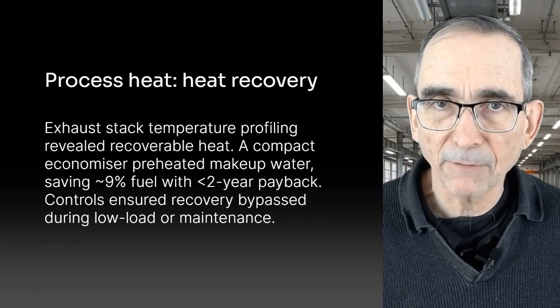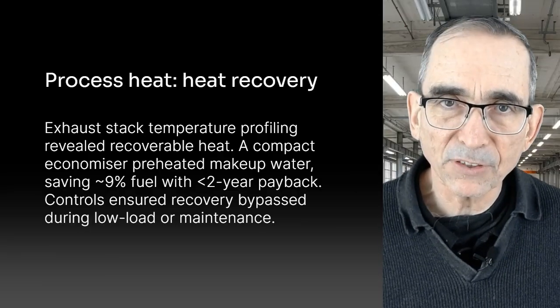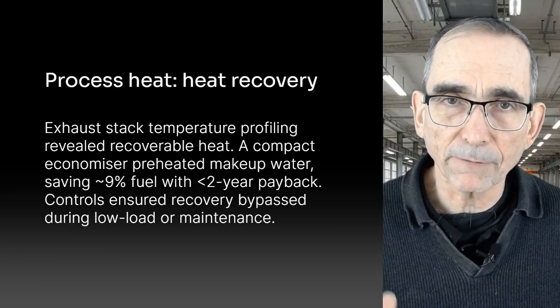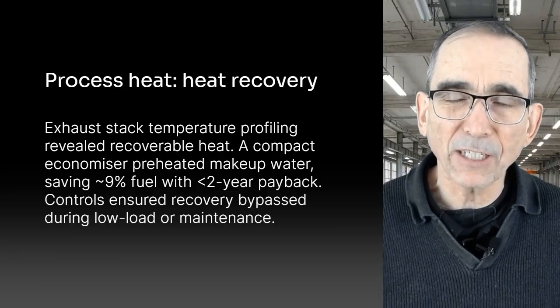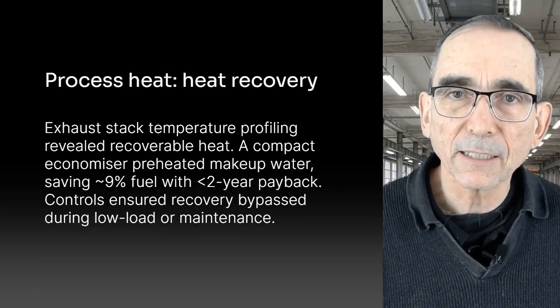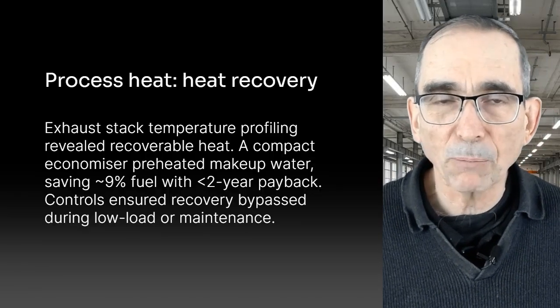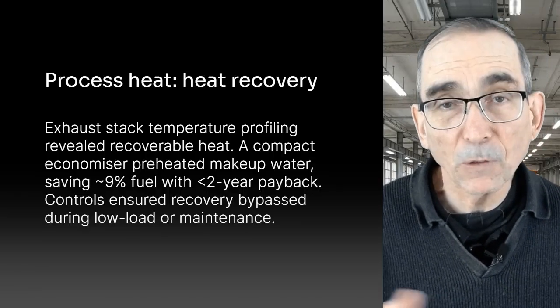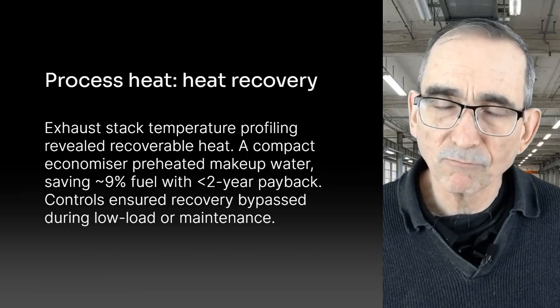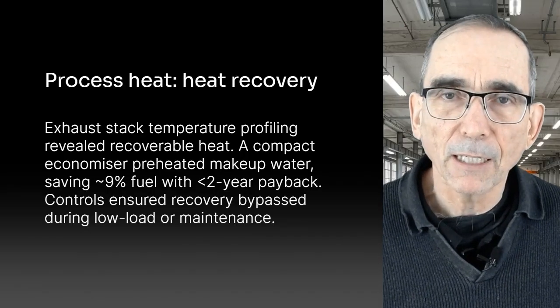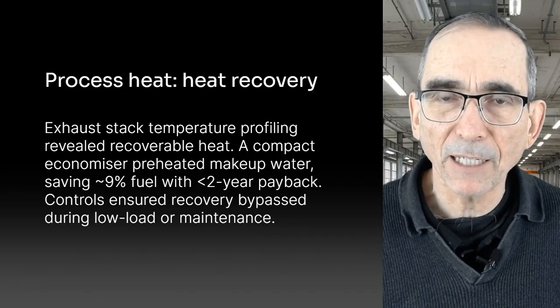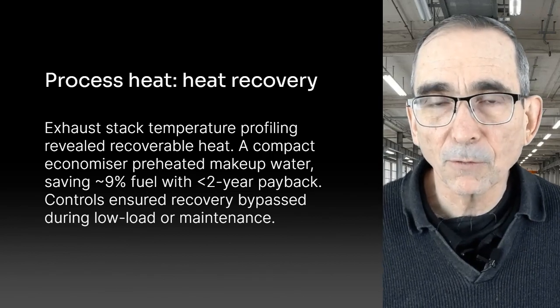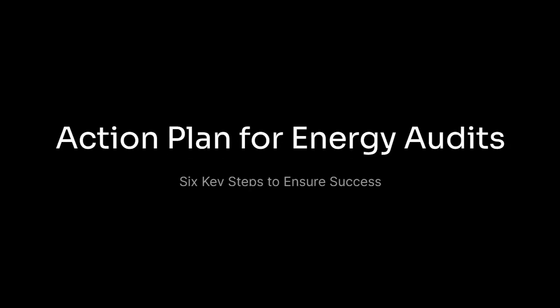And then a process heat recovery example. Exhaust stack temperature profiling revealed there's a lot of heat going up that exhaust stack and being wasted. So a compact economizer, used to preheat makeup water, cut fuel usage by about 9%, and the payback was pretty reasonable on that. Controls ensured recovery was bypassed during low load or maintenance periods. Okay, so each of these improvements was measured, modelled, piloted, and then implemented. Good investment grade behaviour. So what's your action plan?